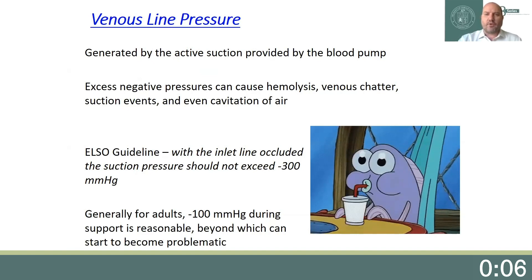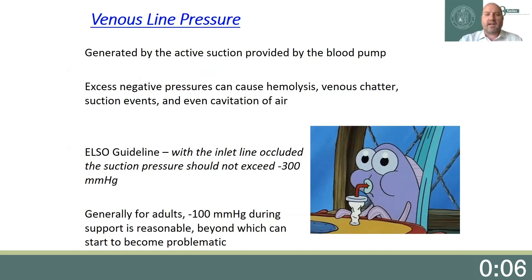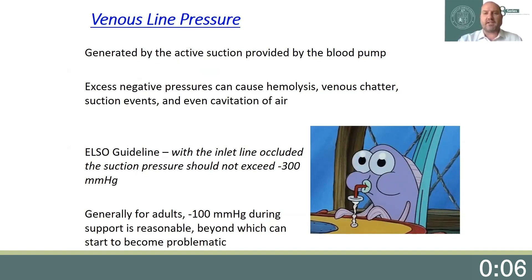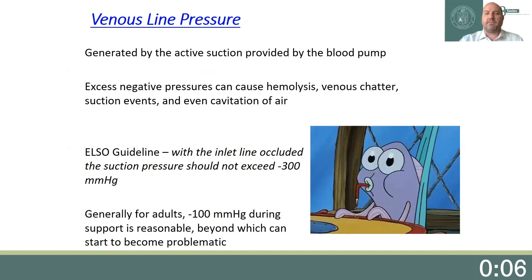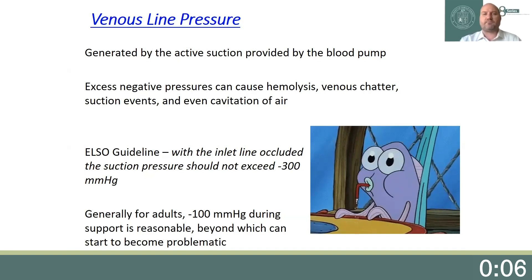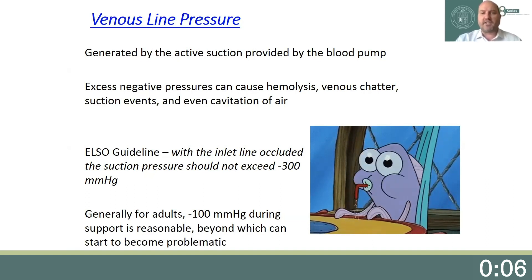Identifying abnormal venous line pressure or pressure trending is important for understanding clinical consequences. Venous line pressure is generated by the active suction provided by the blood pump. Excess negative pressures can cause hemolysis, venous chatter or suction events, and even cavitation of air. These events can occur if the tissue surrounding the cannula gets sucked down around the cannula tip, limiting venous return. ELSO guidelines state that with the venous line inlet occluded, the suction pressure should not exceed negative 300 mmHg. This can be accomplished by keeping pump speed minimal or by using servo regulation to ramp down pump speed in response to excess negative pressure. Generally for adults, most would agree that negative 100 mmHg during support is reasonable, beyond which it can start to become problematic.